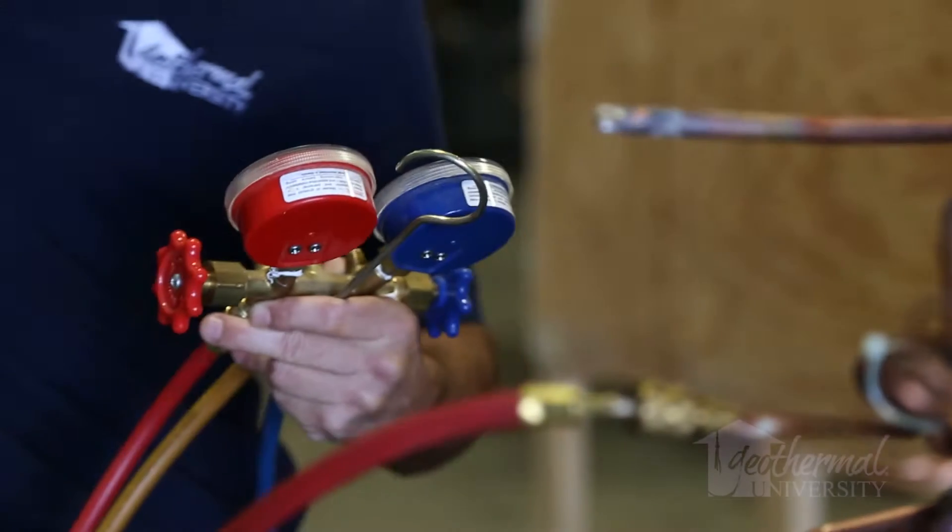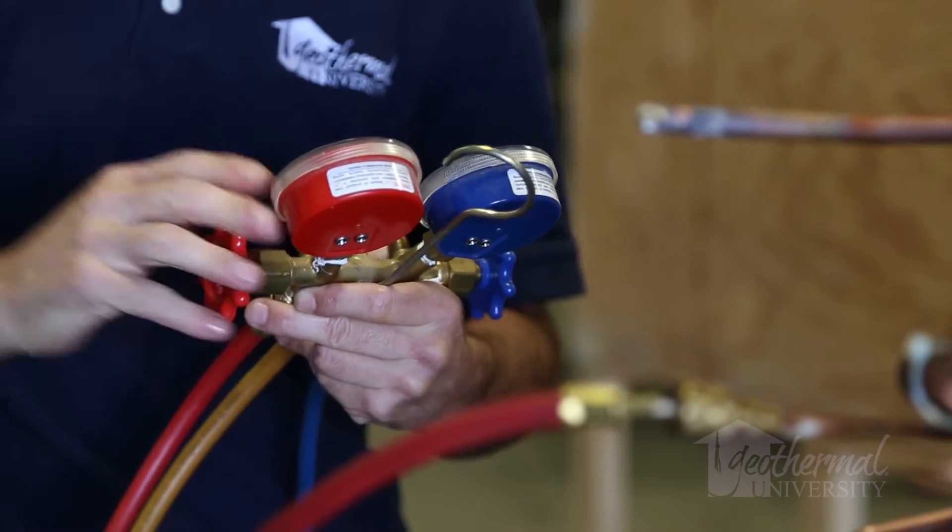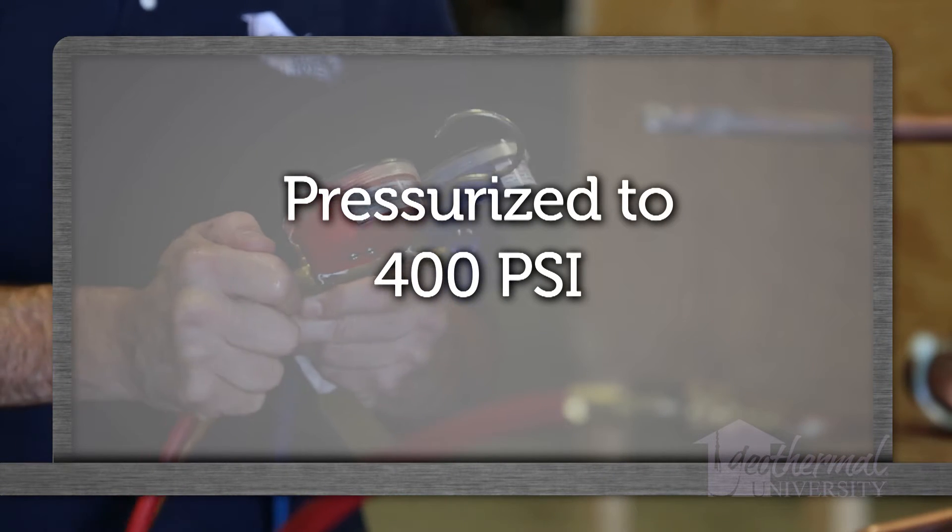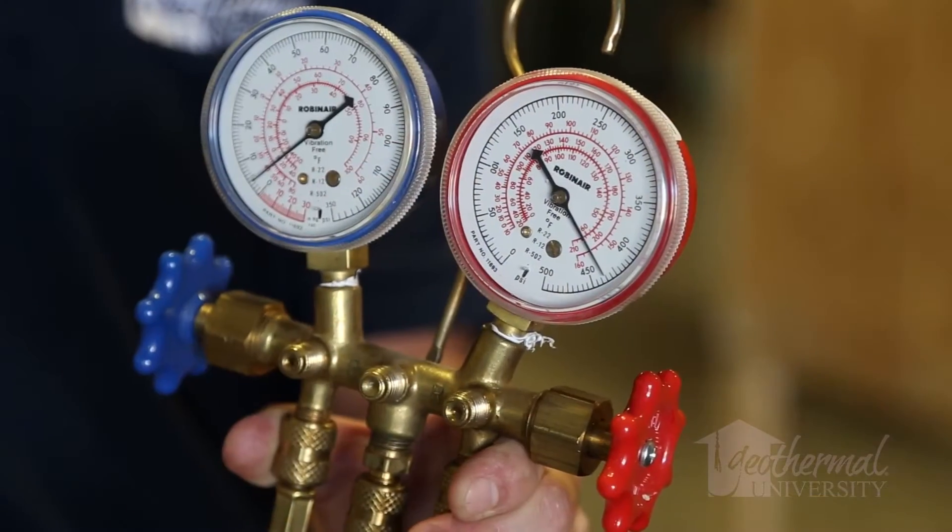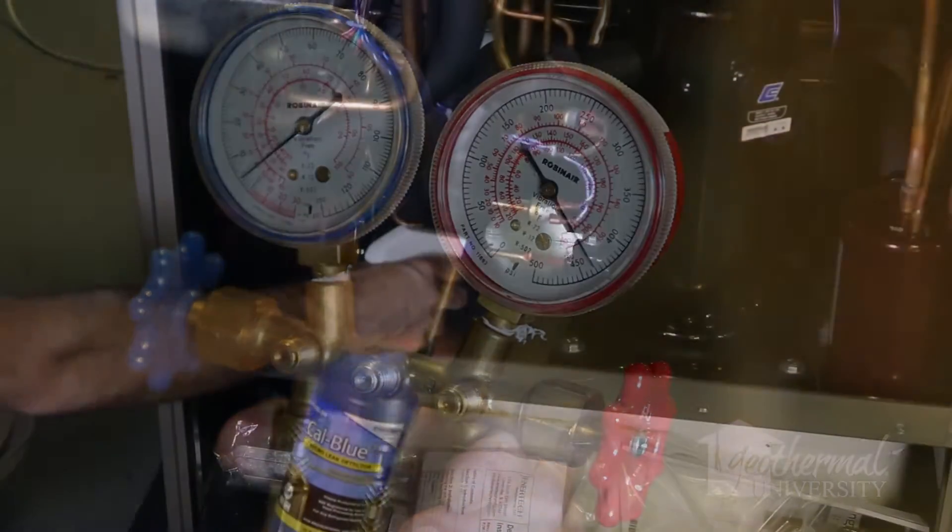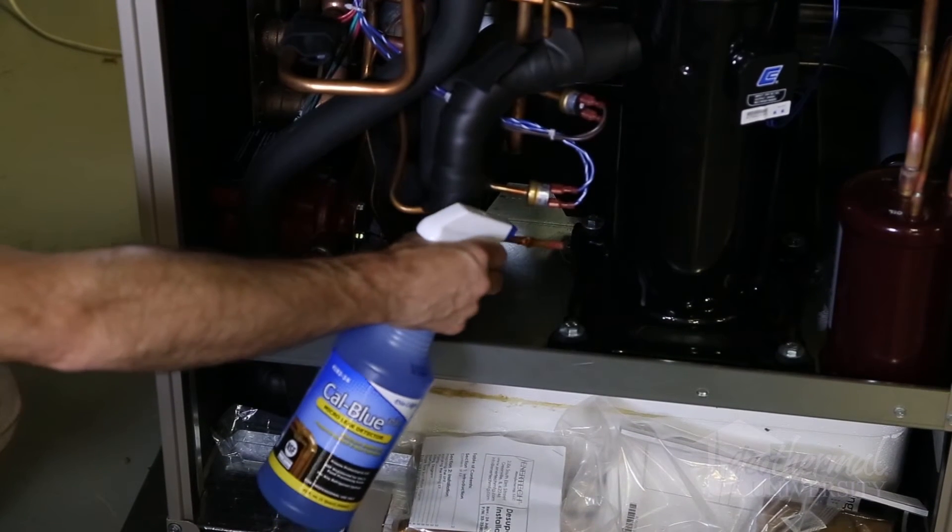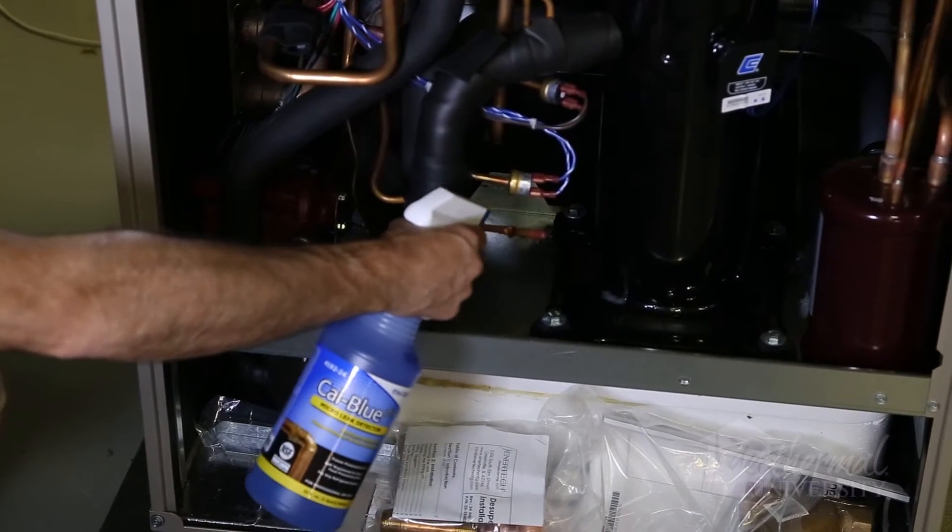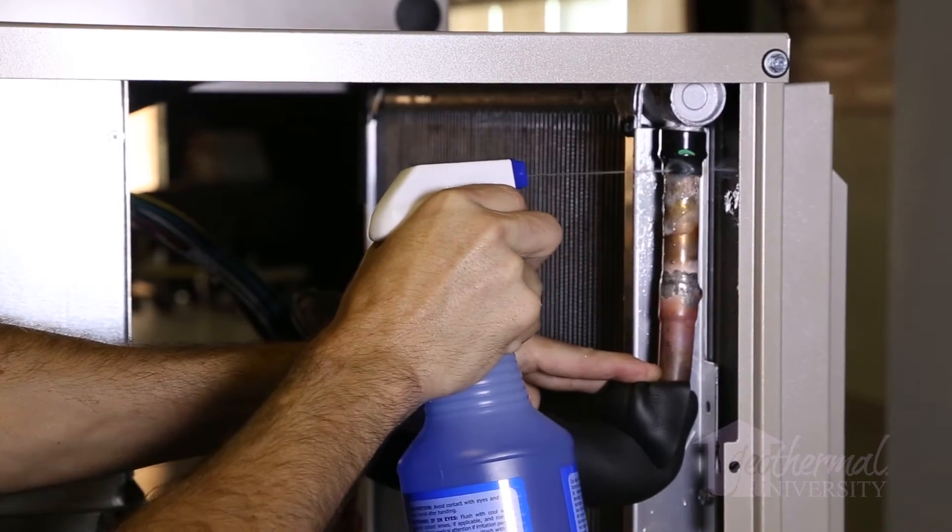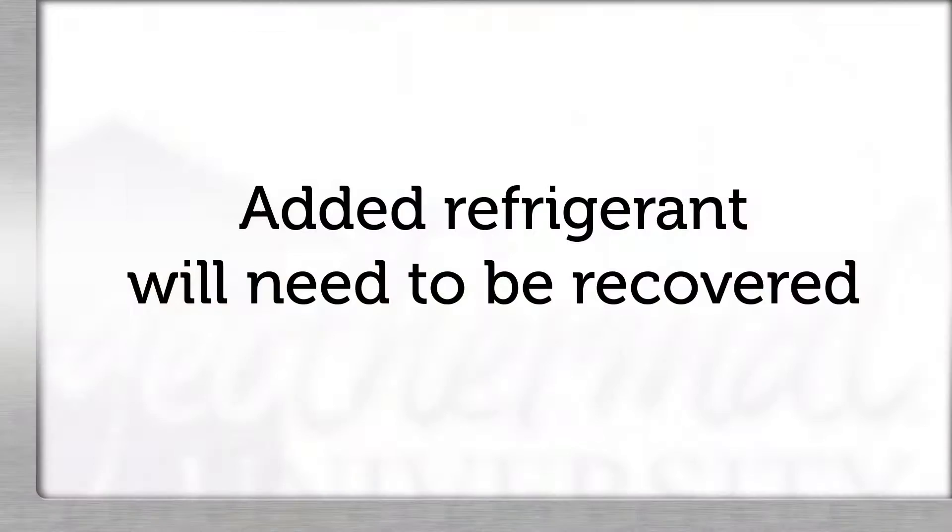Standing leaks are usually large leaks that can be detected with the system off. If the system is flat, the technician may be able to leak check with nitrogen only. The system can be pressurized to 400 psi. It is permissible to add a trace amount of refrigerant along with the nitrogen to perform leak detection. If the system is nearly or mostly flat, we do not recommend adding a full charge of refrigerant or topping off the unit, since a significant leak is likely present and added refrigerant will need to be recovered.